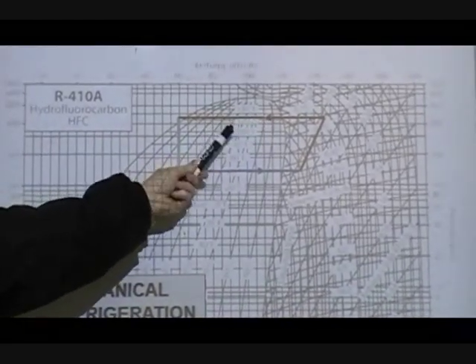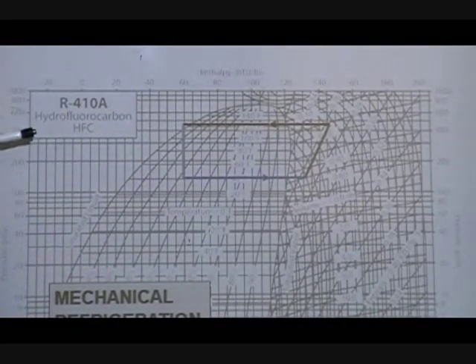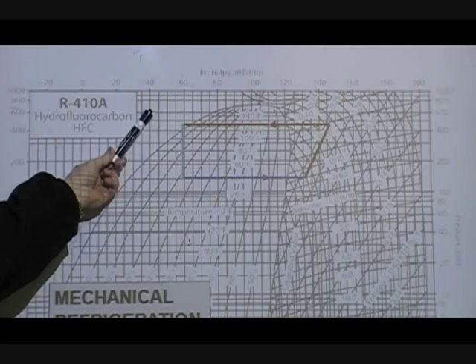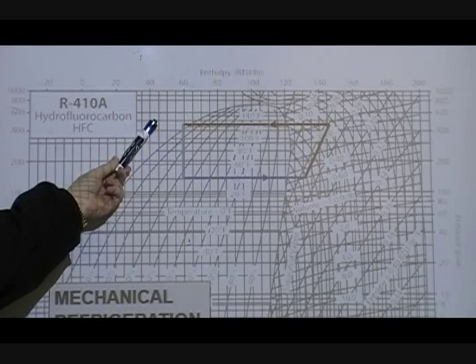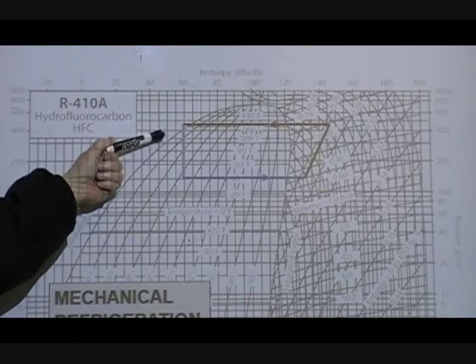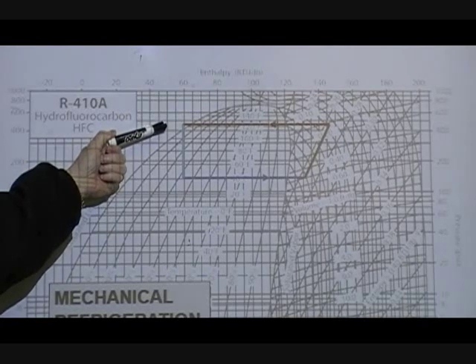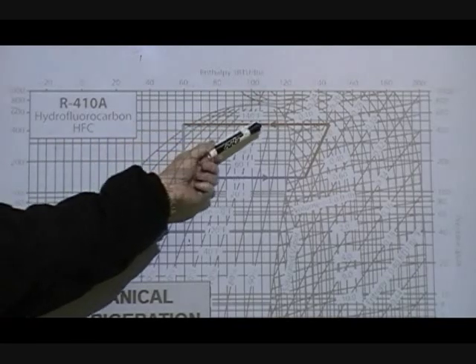Now, you can take this line here, and it's just over 120 degrees. And you come over here, and it's probably, I'm going to interpolate. This line is your 400, and this is probably your 500, this is your 600 PSIA. So I'm going to interpolate. It's just above the halfway mark between 400 PSIA and 500 PSIA. I'm going to say that's probably about 465 or 470 PSIA. And you can convert that to temperature for R-410A. And that's your condensing temperature. And this is your discharge pressure.